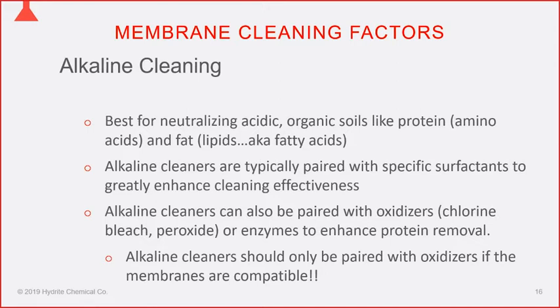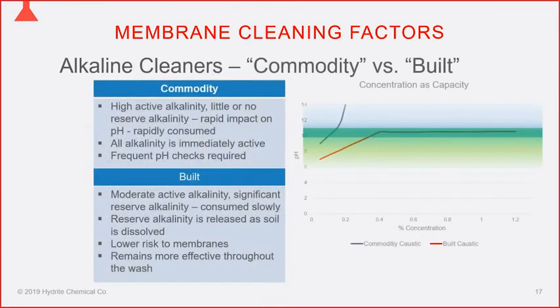Alkaline cleaners should only be paired with oxidizers if the membranes are compatible. Regarding commodity versus built membrane cleaners: as an account manager you're always pressured to cut costs. A commodity caustic is simply sodium hydroxide or potassium hydroxide — nothing else, maybe a touch of gluconic acid as a chelator. When a commodity caustic is put into water, 100% of it ionizes into OH⁻ ions. pH is a measurement of the relative concentration of H⁺ and OH⁻ ions in solution.